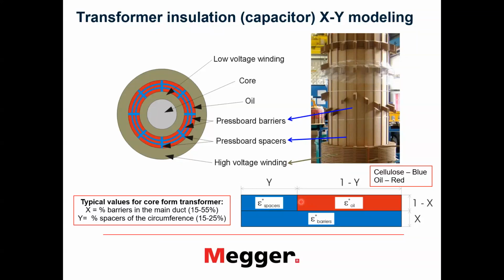All right. Maybe another question. One thing in that regard, we have to differentiate power factor testing from DFR testing. Power factor may require some trending analysis to see what the degradation process has been. When you talk about DFR, it's an instantaneous characterization of the condition as found of the transformer. So what you see is what it is at that moment. You don't need to do a trending analysis. You measure, and you understand what's happening at that moment in that transformer, okay? All right. Because that was on different chats and I tried to combine them all together into one to deliver that question.